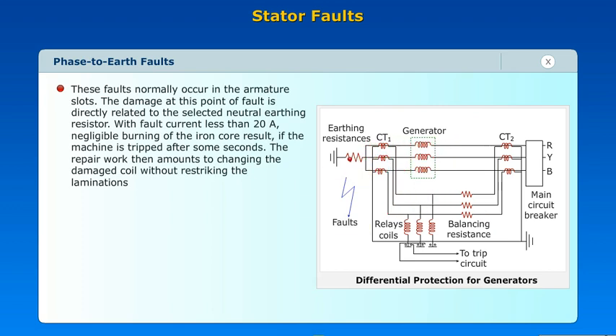The damage at the point of fault is directly related to the selected neutral earthing resistor. With fault current less than 20 amperes, negligible burning of the iron core results if the machine is tripped after some seconds. The repair work then amounts to changing the damaged coil without restriking the laminations.